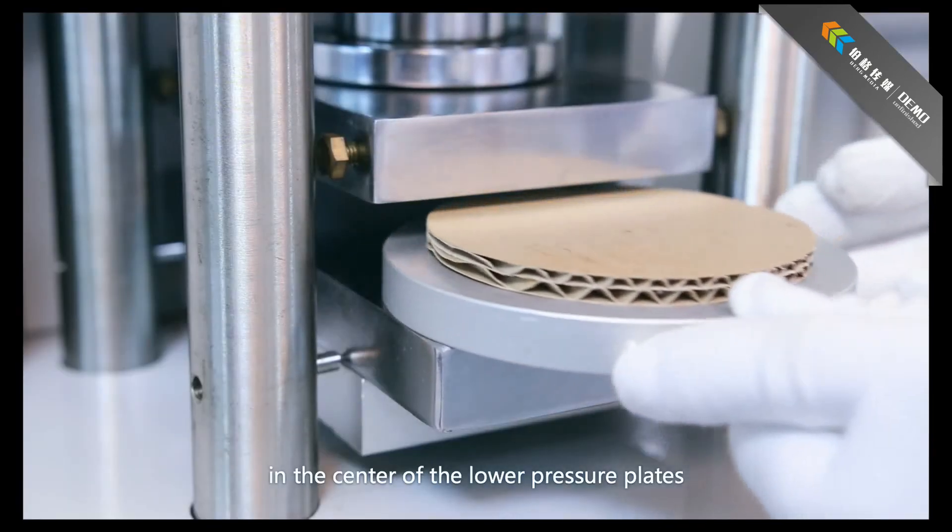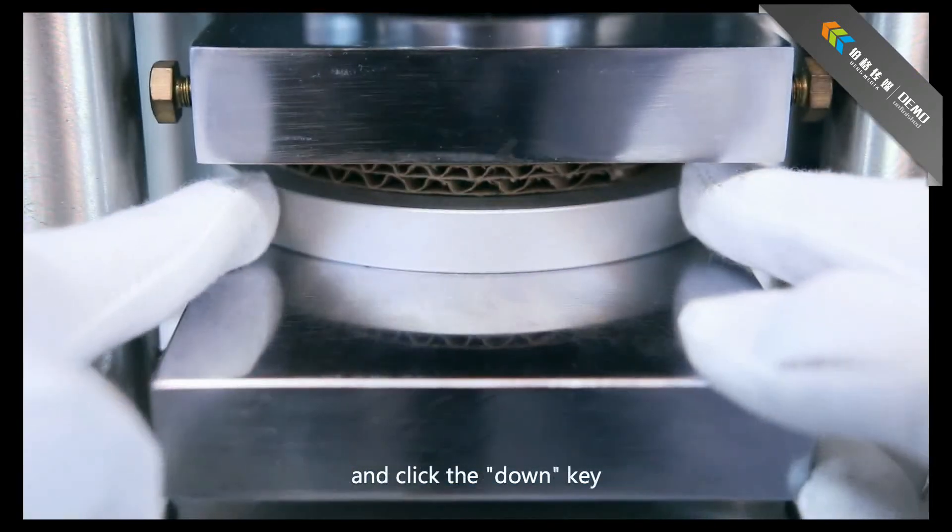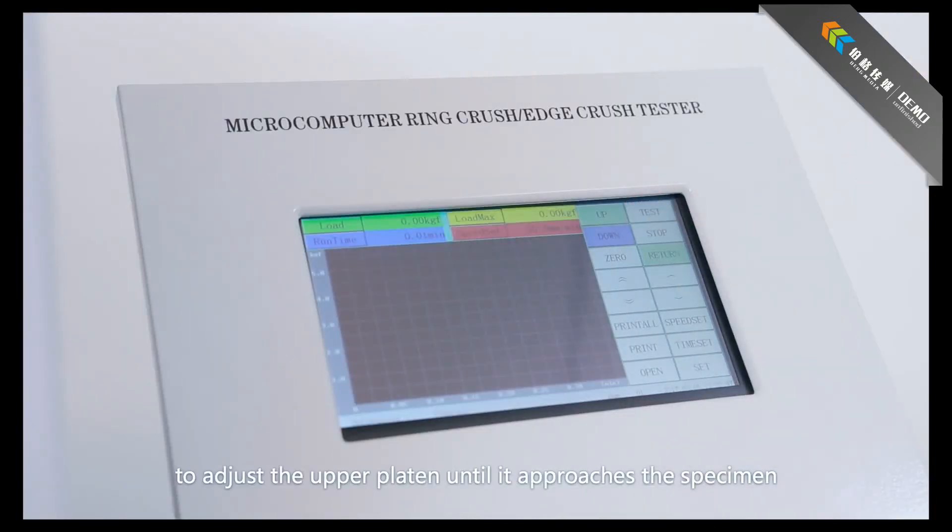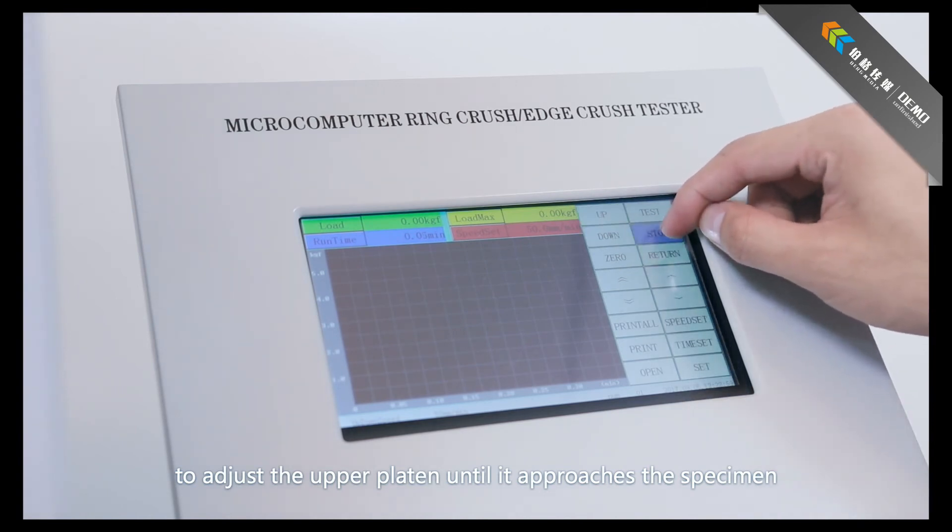Place the specimen holder in the center of the lower pressure plates, and click the down key to adjust the upper platen until it approaches the specimen.